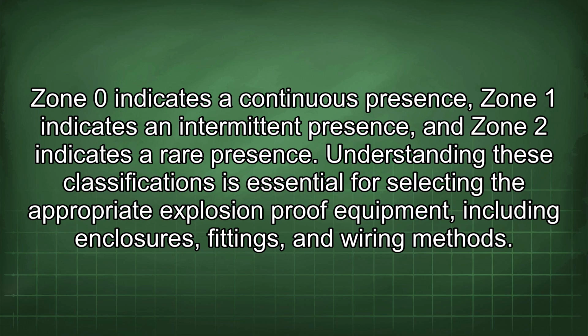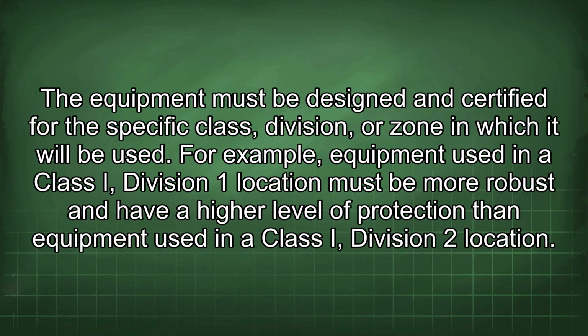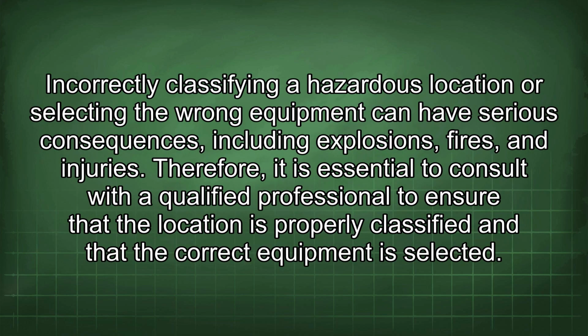Understanding these classifications is essential for selecting the appropriate explosion-proof equipment, including enclosures, fittings, and wiring methods. The equipment must be designed and certified for the specific class, division, or zone in which it will be used. For example, equipment used in a Class I, Division 1 location must be more robust and have a higher level of protection than equipment used in a Class I, Division 2 location. Incorrectly classifying a hazardous location or selecting the wrong equipment can have serious consequences, including explosions, fires, and injuries. Therefore, it is essential to consult with a qualified professional to ensure that the location is properly classified and that the correct equipment is selected.